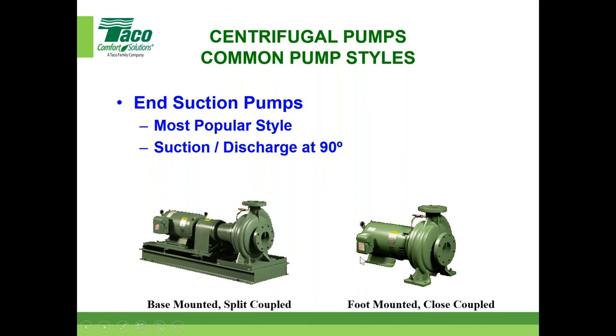Personally, I would not specify a close coupled pump over 10 to 15 horse. These motors get very, very heavy, very quickly, horsepower wise, and from an engineering standpoint, the maintenance guys are going to have an issue down the road. But us pump manufacturers offer this type of arrangement up to 60 horse because this is a JM style motor, and that motor frame goes up to 60 horse, and it's used in different applications, not just for pumps.